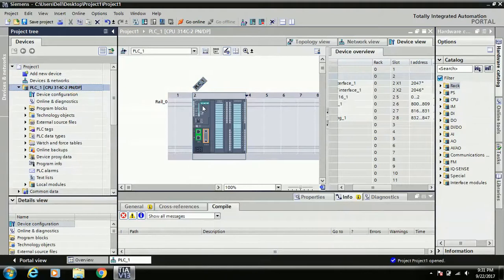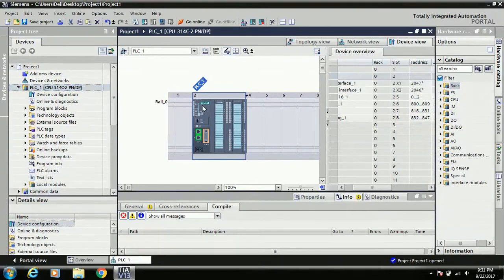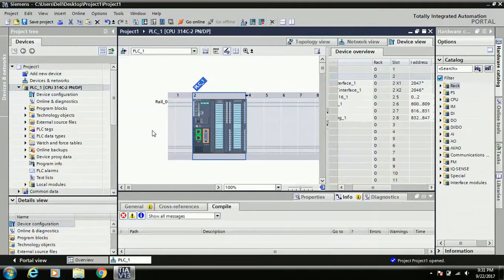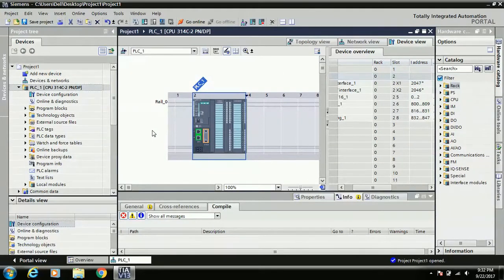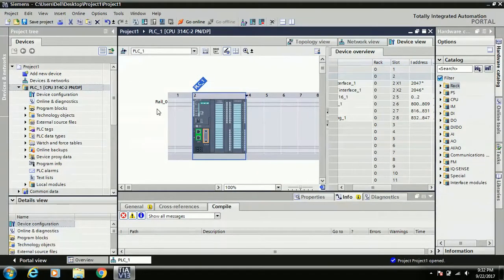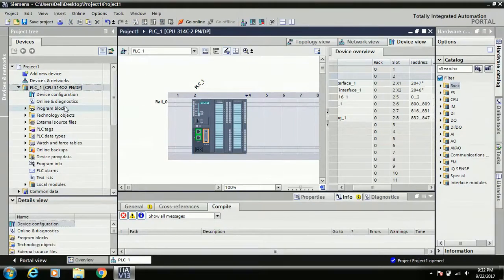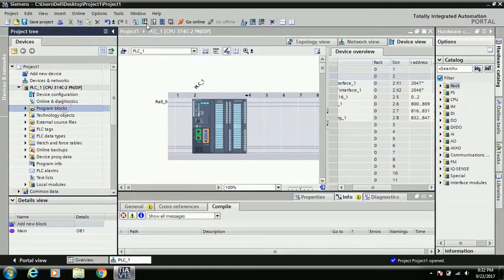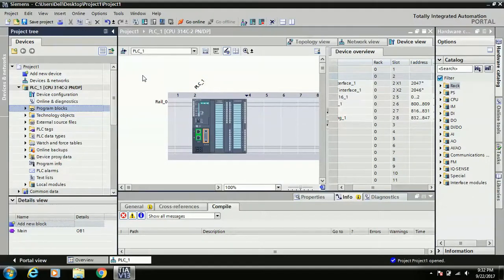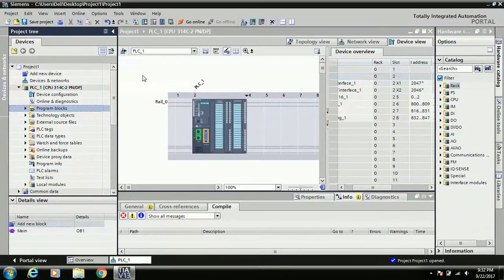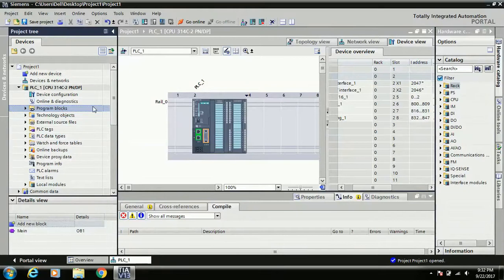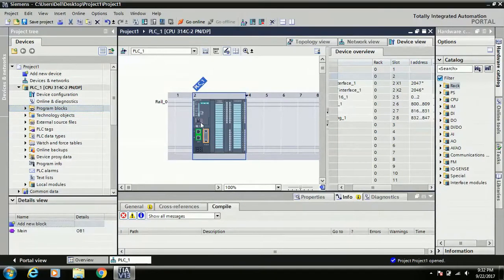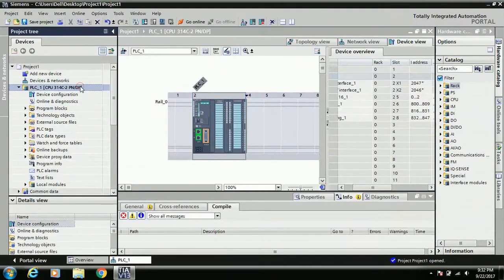Your second option - just click on this option, because you will do the download process using these two options. Your PLC is updated with system blocks, data blocks, and program blocks. All the memories and data blocks can be updated with the PLC. If you just click on the program block and try to download, in this case only the program block is updated - your PLC properties is the last one, not the current one. So please always remember, your first time you download, click on this PLC.